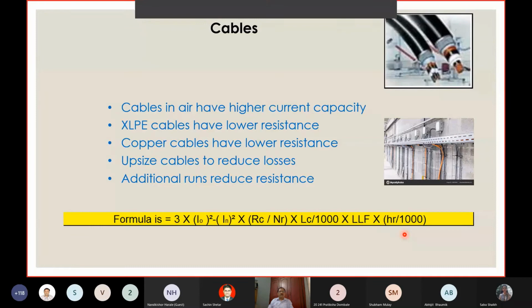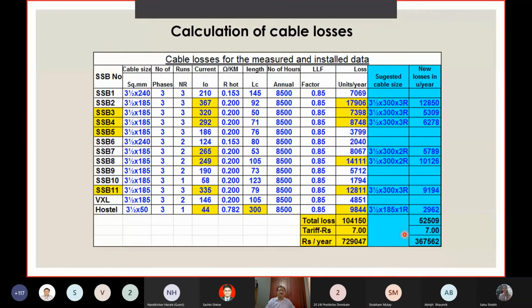Nowadays, the fashion is to use a lot of XLPE cables rather than PVC cables because of the long life. We recommend copper cables because of the pliability and lower cross section, so that the losses can also be minimized. We have already discussed the opportunities available for reducing I2R losses by upsizing the cable sizes or using additional runs of cables. If you look here, I wish I had shown one more slide similar to this. This is a textile mill.